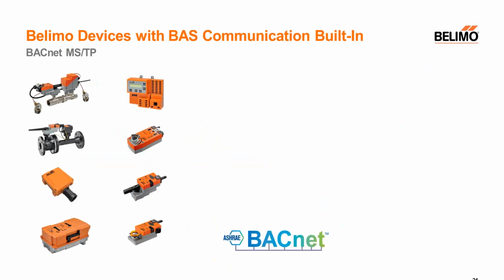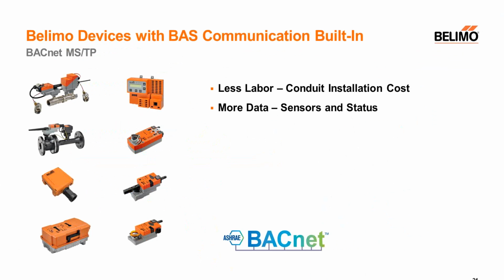We have a number of Belimo devices with BACnet communication built into them. From a features and benefits standpoint, in some instances, there's a significant labor savings that you could enjoy, particularly on something like a built-up air handler, where you have a lot of devices and a lot of conduit. And running a bus around the package of an air handler is much more efficient than a lot of home runs. We live in a world where data is important, so the more data you can get, instead of just telling an actuator what to do with a voltage signal, if you can get a local sensor, if you can see status of the actuator, feedback of the actuator, all that is beneficial. In some cases, maybe you're out of I/O on your building controller and you need to add something to a system. Well, you don't need I/O to use all these actuators.